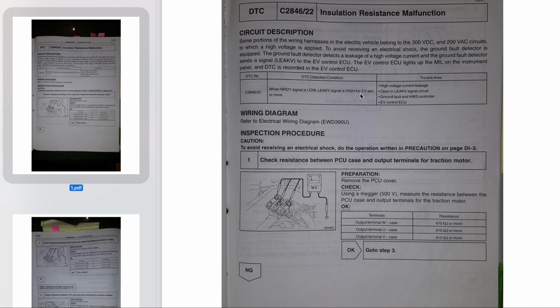So what the repair manual has you do is check the insulation resistance with something called a megger, and what it does is it provides a high voltage to the cabling, and it checks for current going from the megger through the cabling back to the megger by way of the ground. If that's happening over a certain amount, in this case, the resistance should be 410 kiloohms or more. If it's less than that, then that's an unacceptable amount of leakage through the insulation. So that's the way they do it.